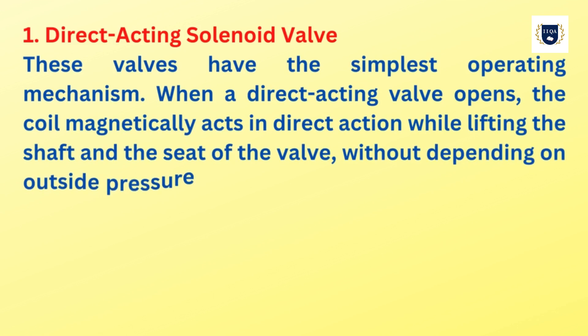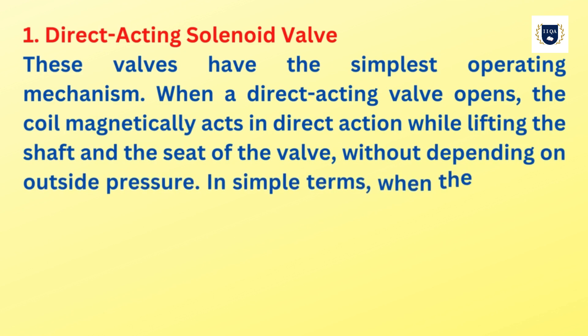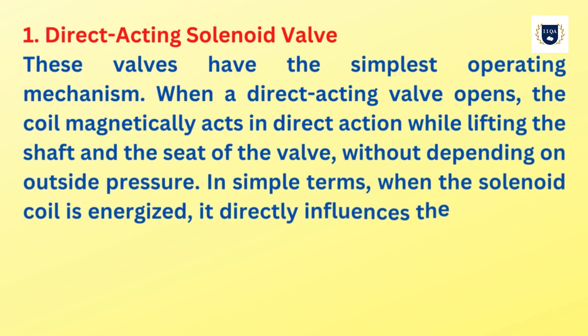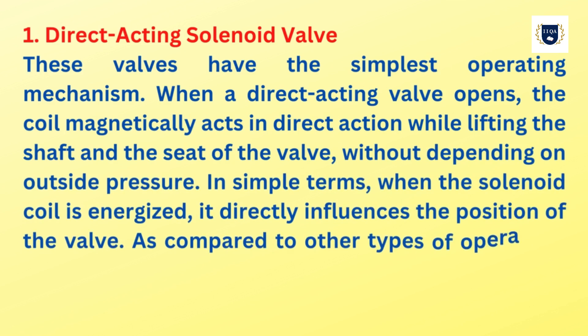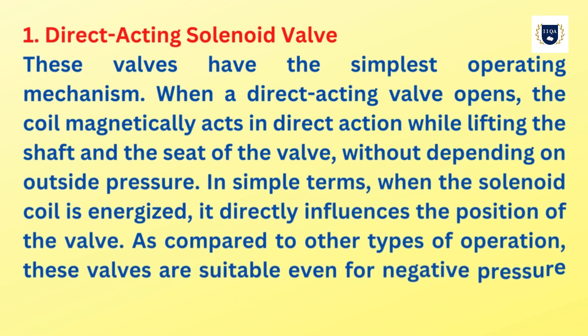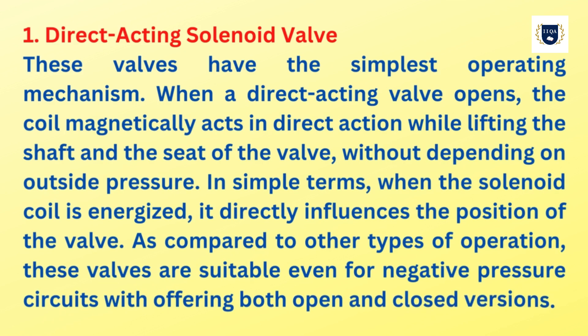When a direct acting valve opens, the coil magnetically acts in direct action, lifting the shaft and the seat of the valve without depending on outside pressure. In simple terms, when the solenoid coil is energized, it directly influences the position of the valve. These valves are suitable even for negative pressure circuits, offering both open and closed versions.